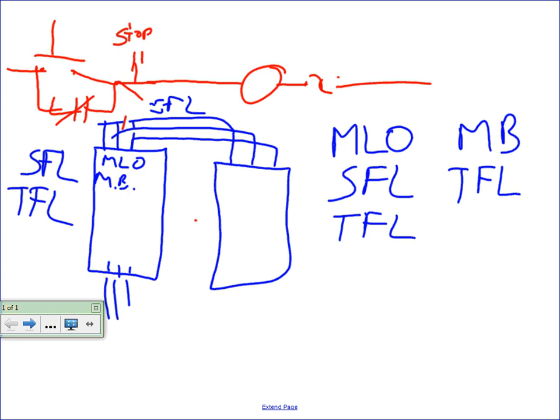Because code requires it, because you're deriving a new system. You're going from 480 to 208, and as soon as you derive a new system, you have to bond it. You've got to treat it like a service, basically. So you have to provide a main breaker panel at that point. Okay.